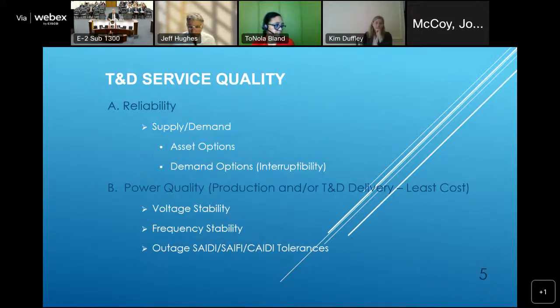SAIDI, SAIFI and CAIDI are all valid measures, but you heard some discussion by Mr. Maley about what's a momentary outage—momentary are the ones below one minute. For industrial customers, harm can happen within a second. So we should consider another measure, MAIFI, momentary average interruption frequency index, which is the total of momentary outages in a year divided by the number of customers.